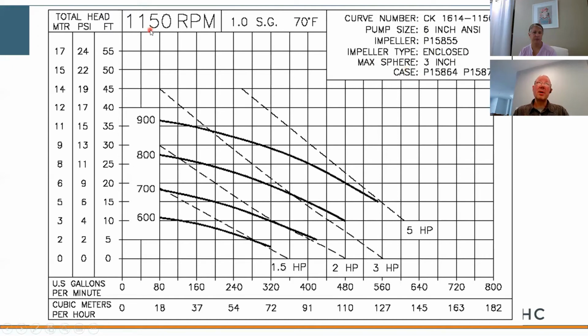With HVAC pumps, we tend to stay away from 1150 RPM, unless we're worried about NPSH or an open basin with atmospheric pressure that's low. But on Sump and Sewage, it's not uncommon to see 1150 because a lot of our pumps don't require much head pressure. They just require some flow. Okay, and that doesn't affect our lead time as bad as it does on the HVAC side.